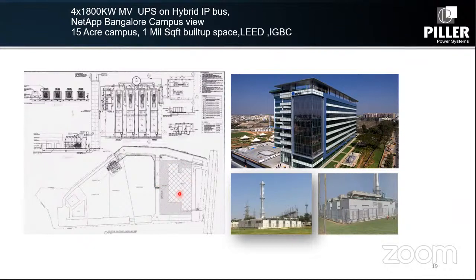We have eliminated almost 150 tons of air conditioning, and we were able to save almost 7,000 to 8,000 square feet for NetApp. Now, NetApp is not a colo provider. When we do the comparison for a complete data center, 20 megawatt, you will see tremendous savings. But this has already been running. We are very thankful to NetApp for giving us this opportunity.